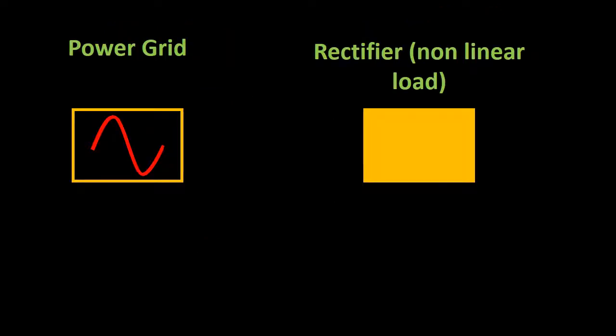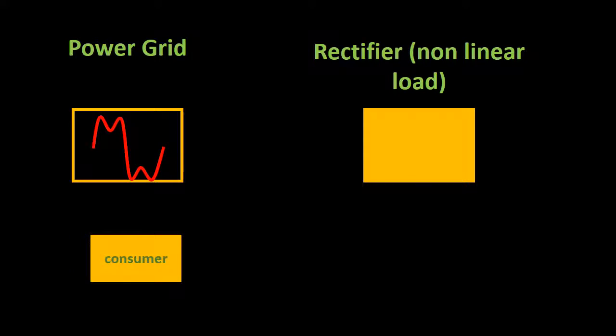This manipulation of the waveform is why a rectifier is considered to be a non-linear load. Non-linear loads reflect power back into the grid at various frequencies and phases, referred to as harmonics. Harmonics interfere with the incoming power to create a distorted waveform on the grid. Other consumers will have to put up with this distorted grid waveform.